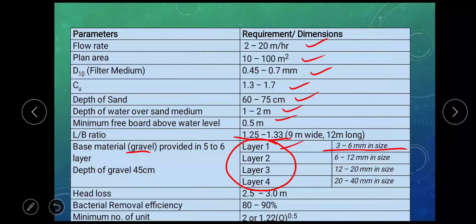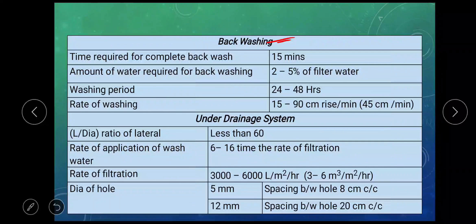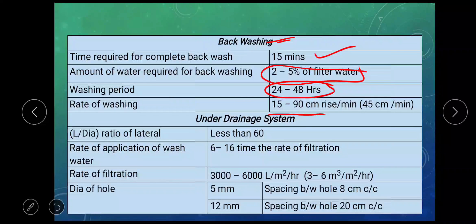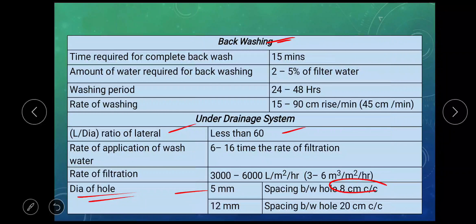In layer 1, 3 to 6 mm size of the particle may be used. In layer 3, 12 to 20 mm size of the particle may be used. In layer 4, 20 to 40 mm size of the particle may be used. The depth of the base material may vary from 45 to 50 centimeter. Head loss may vary from 2.5 to 3 meter. Bacterial removal efficiency is 80 to 90 percent. Minimum number of units can be calculated as 1.22 times Q to the power 0.5, or simply 2. Backwashing is done every 1 to 2 days for 15 minutes using 2 to 5 percent of the filter water. Rate of backwashing may vary from 15 to 90 centimeter rise per minute. For the under drainage system, length to diameter of lateral should be less than 60. Rate of application of wash water may vary from 6 to 16 times the rate of filtration. Diameter of hole in lateral may be 5 mm when spacing provided is 8 centimeter center to center.